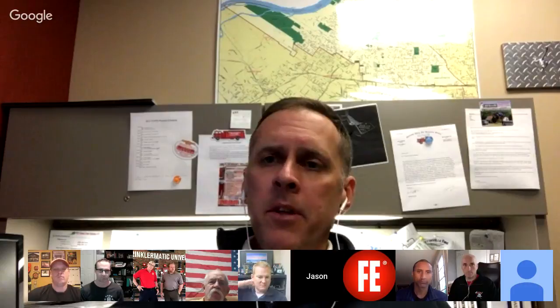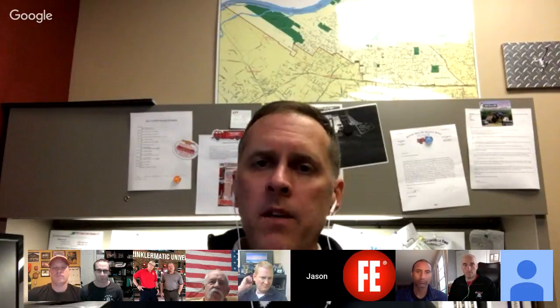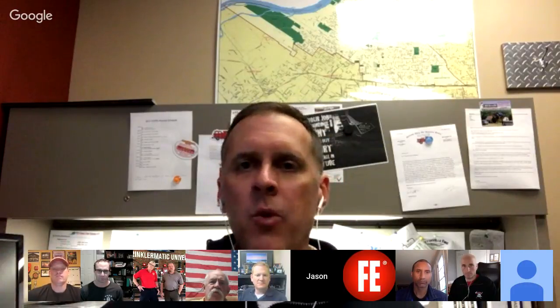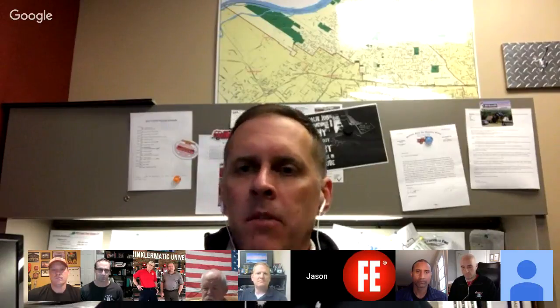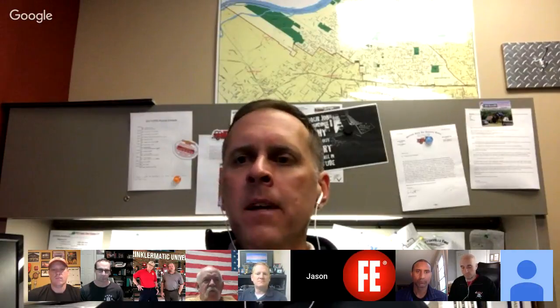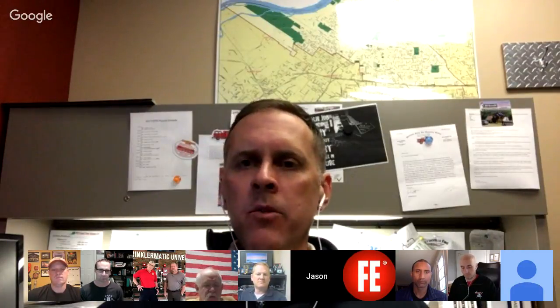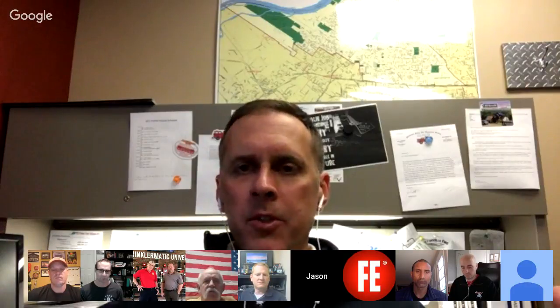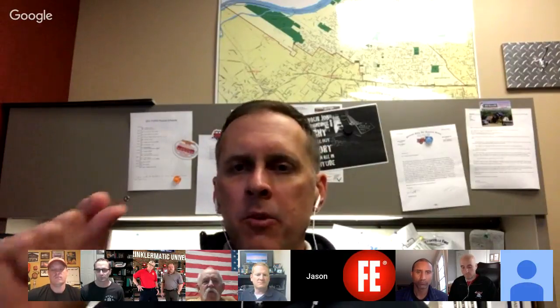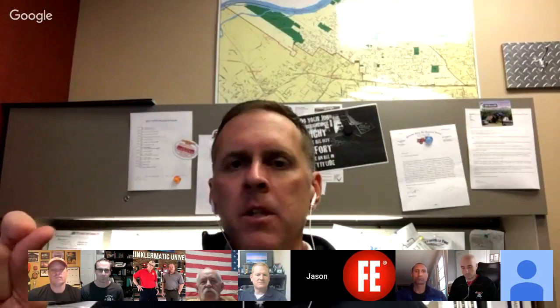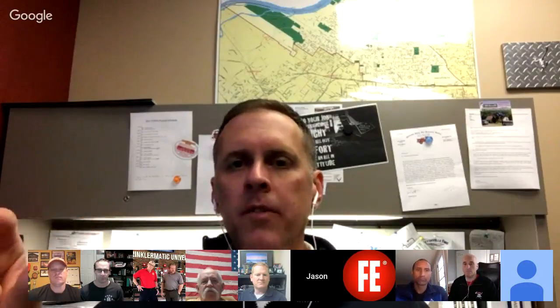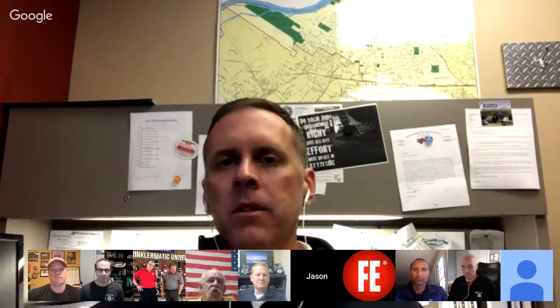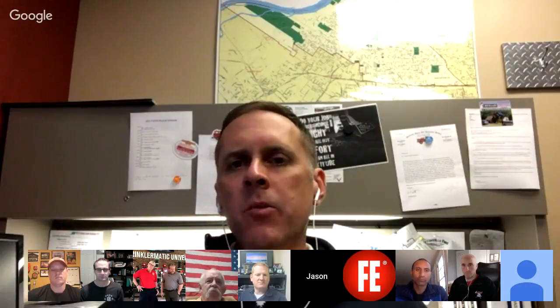The system they put in place, as I was telling Bill earlier, they keep adding these gas houses, which is where they actually fill the gas before the product goes online. The systems in those rooms are deluge type systems, and the most minuscule flash will set the entire room off and completely deluge it. It's pretty amazing to see what it can do.